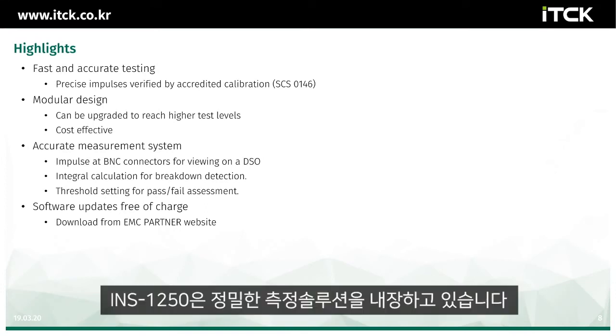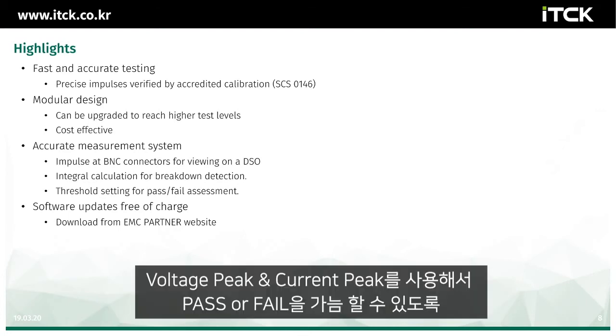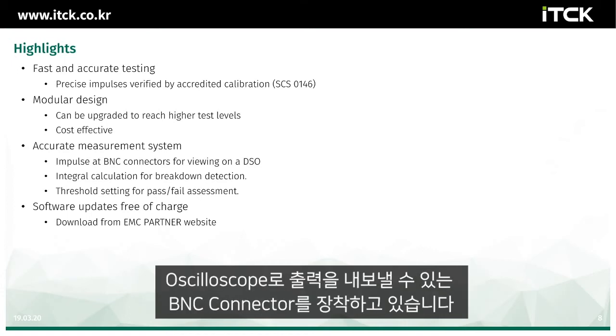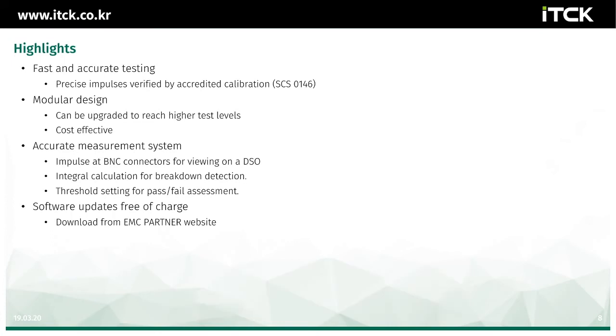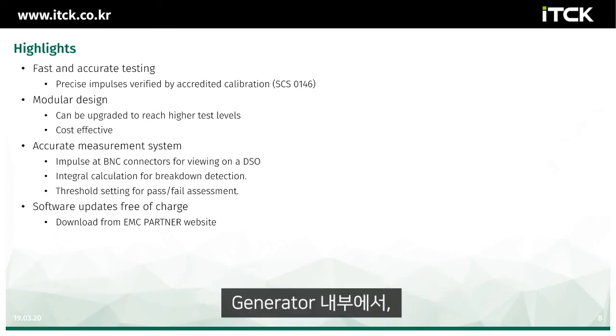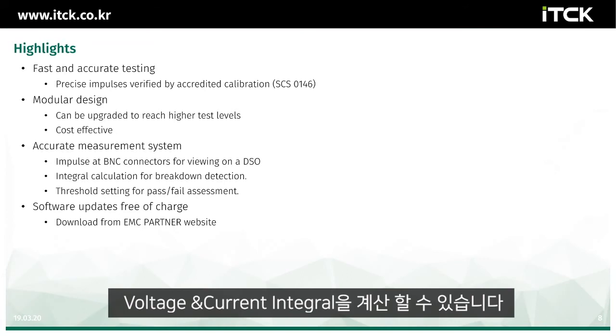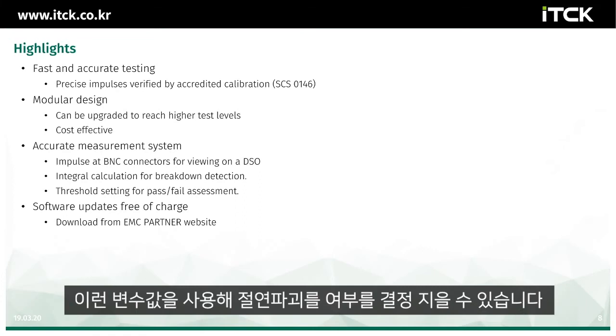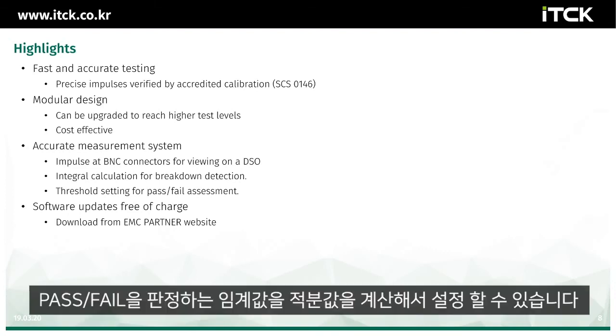This offers a cost-effective solution for those customers who wish to increase their test level. Offered with the INS 1250 systems is an accurate measurement solution. We can bring the voltage and current impulses to the BNC connectors on the front panel, where they can be viewed on an oscilloscope and assessed for pass or fail using the peak of the voltage and current. Within the generator, we make a calculation of the voltage and current integral, and those parameters are used to determine breakdown detection. A threshold setting for pass or fail is entered using the integral calculations.